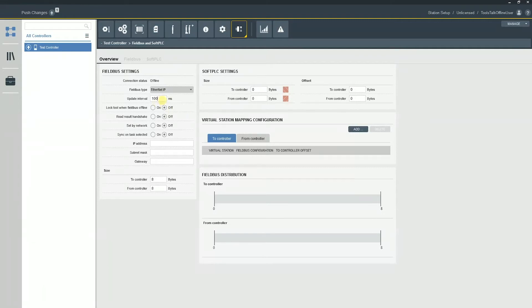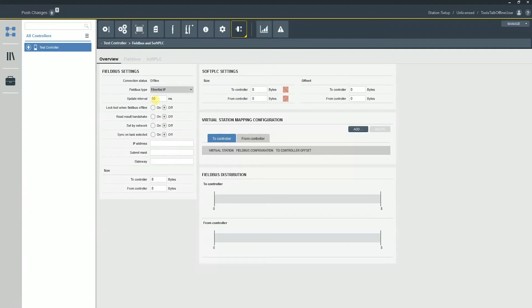Typically, what I recommend for update interval is to match the scan rate of the PLC. So for instance, if a PLC is scanning at a rate of once every 50 milliseconds, I typically recommend that you mirror that. So try to mirror that update interval with the scan rate of the PLC.